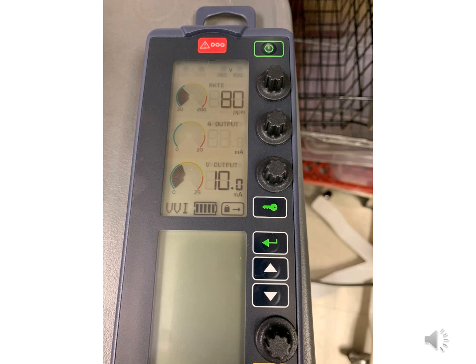The second one controls the output if you have atrial wires. That currently is turned off, and you can see how it's a little faded. The third dial corresponds to the ventricular output, and you can see that there at 10. Underneath that third dial, you see a little key, and you have to press that in order to make any adjustments on the pacemaker. You see right next to the key, there's a little lock symbol with a point to the key. That's currently telling you that the pacemaker is locked, and you need to unlock it to make any adjustments.